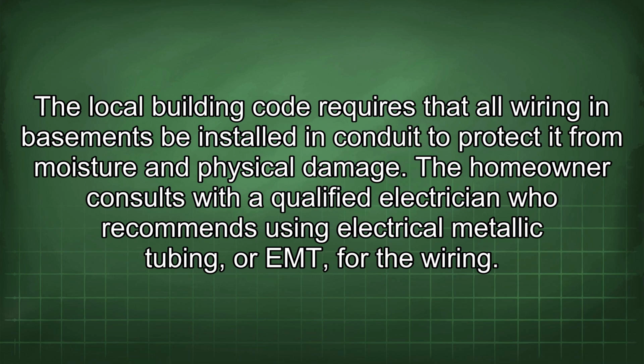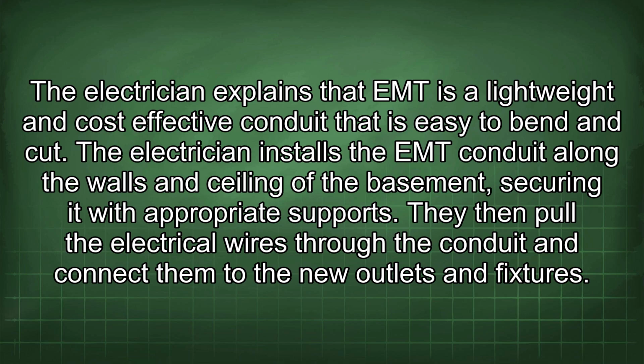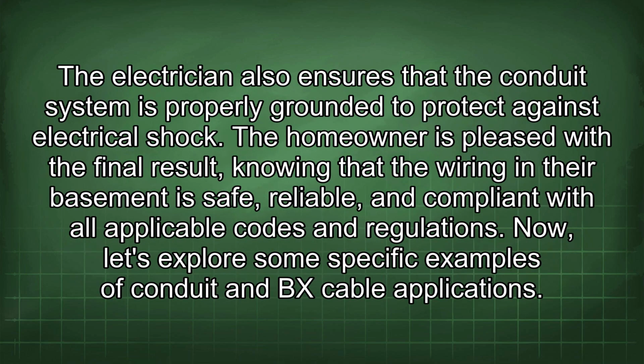The homeowner consults with a qualified electrician who recommends using electrical metallic tubing, or EMT, for the wiring. The electrician explains that EMT is a lightweight and cost-effective conduit that is easy to bend and cut. The electrician installs the EMT conduit along the walls and ceiling of the basement, securing it with appropriate supports. They then pull the electrical wires through the conduit and connect them to the new outlets and fixtures. The electrician also ensures that the conduit system is properly grounded to protect against electrical shock. The homeowner is pleased with the final result, knowing that the wiring in their basement is safe, reliable, and compliant with all applicable codes and regulations.